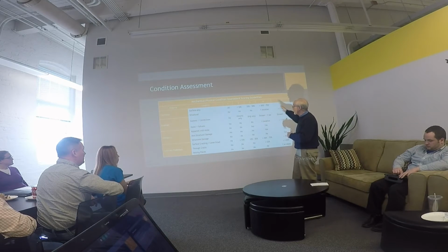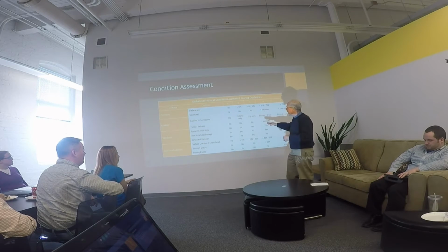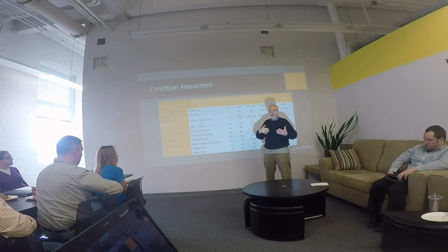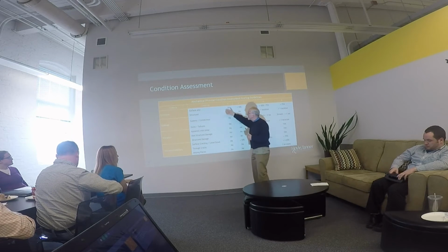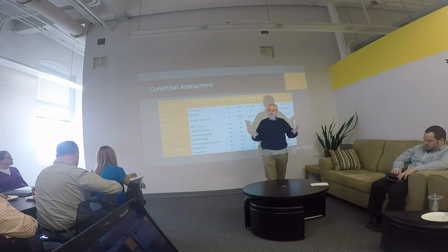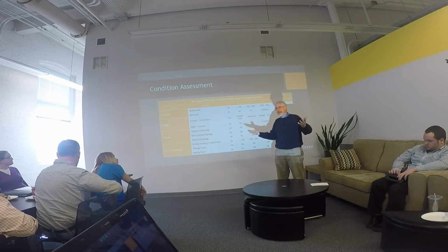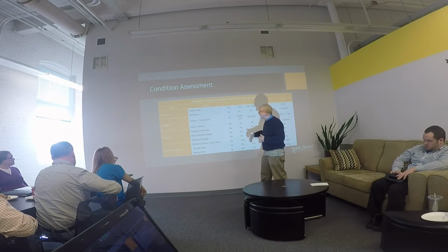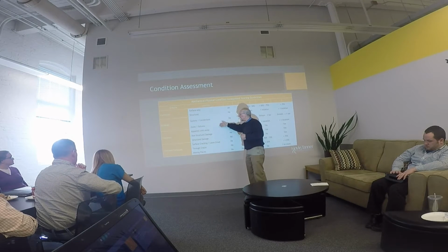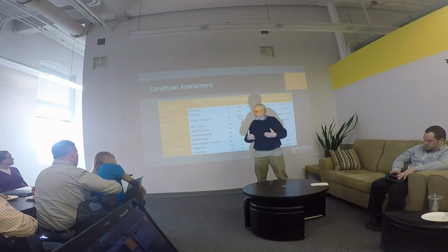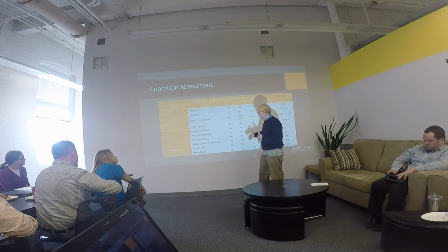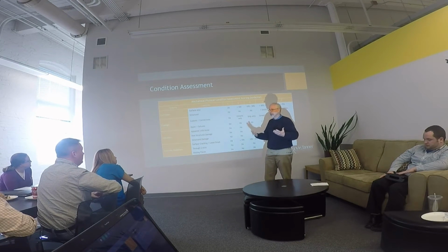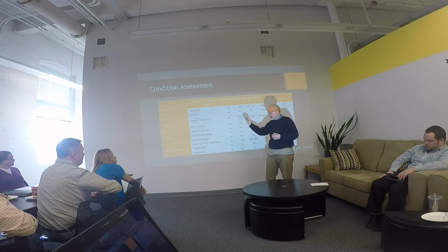So here's a physical condition board, and we're looking at corrosion on the surface, structural, and different things that are operational. Surface rust is operational. You didn't maintain it. You didn't paint it and get to it before it rusts apart. And then, does it have leaky gaskets? Those are structural. So at what point is it acceptable? Vibrations are indicators, meaning the worse the vibration, the less likely it's going to live, and it's going to move out on the structure.